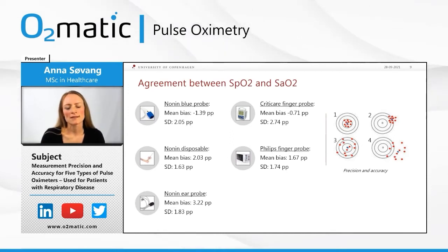If we instead look at the standard deviation, SD, we can see that Criticare had the highest standard deviation. And this implies that Criticare was the most imprecise. If we look at the targets here, illustrating precision and accuracy, you can see number 1 is precise and accurate. Number 2 is still precise, however inaccurate. Number 3 is accurate but imprecise, and number 4 is both inaccurate and imprecise. And we could say that Criticare corresponds to number 3, and the others are somewhere between 2 and 4. This is just to illustrate how both imprecision and inaccuracy can cause an uncertain measure.